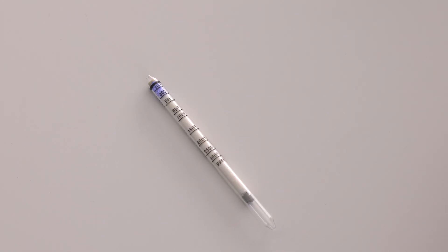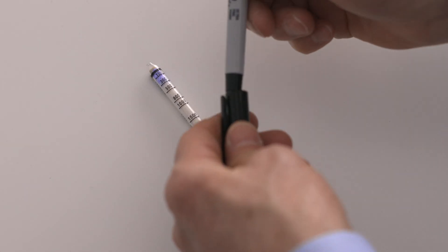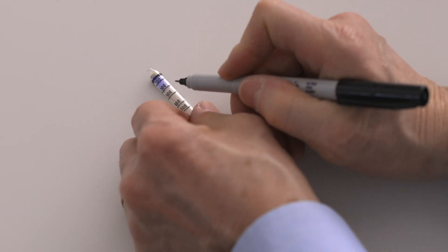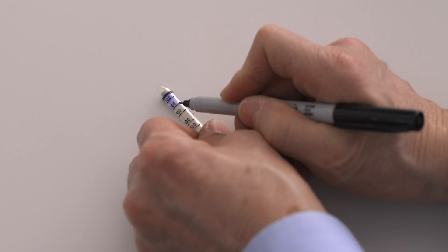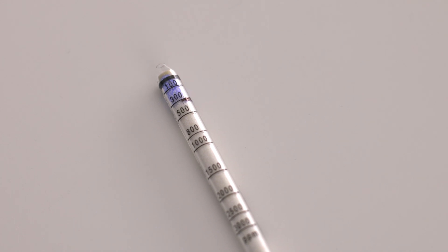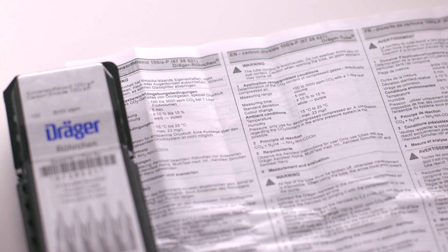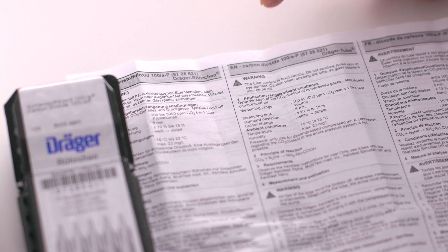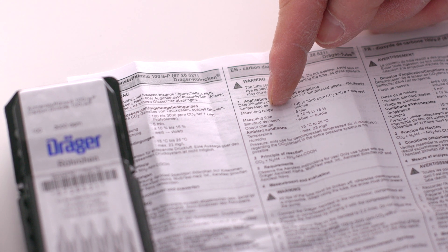Start with the carbon dioxide tube. Using an indelible marker, mark the end point of the bluish-violet discoloration. Always read the total length of the slightest discoloration on a detector tube. In this case, the discoloration reached 300 ppm. There are instructions for reading the results inside the package of each tube.